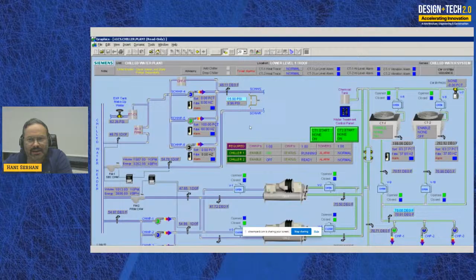So the maintenance team can act on it immediately. Also, we can extract a lot of data from it about energy consumption across the year, and from that we can analyze the data and find out how to optimize the system. For example, electricity at peak time is usually very expensive, so one of the things the BMS system can help with is monitoring consumption at peak time. It can be automated such that it will divert to, let's say, solar power energy or inverters with battery, to go off the grid at peak time and reduce the bill from the main utility.